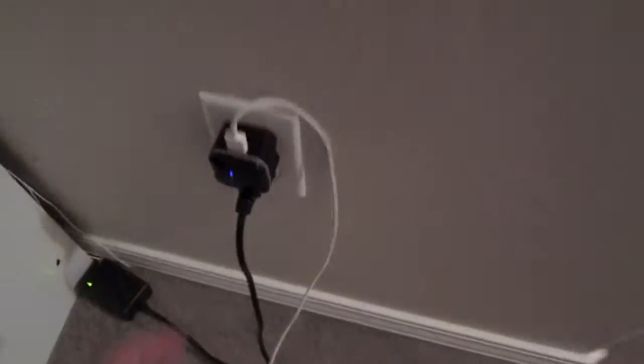Let me just demonstrate. So you pull the plug, and as you can see, the yellow light comes on, the power light goes off, and the sound. The trouble silence button will disable the buzzer but keep the light on.